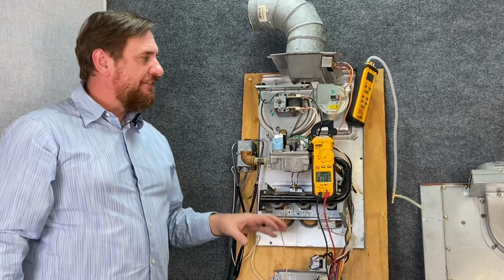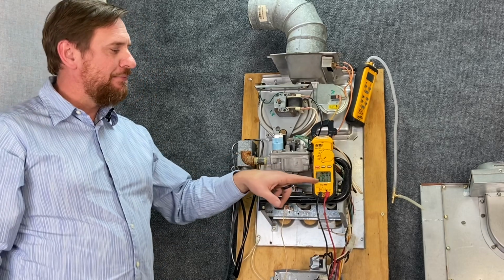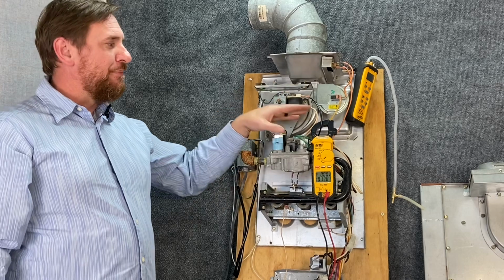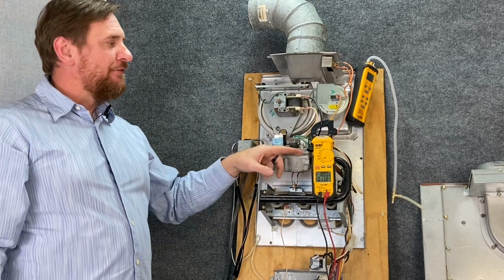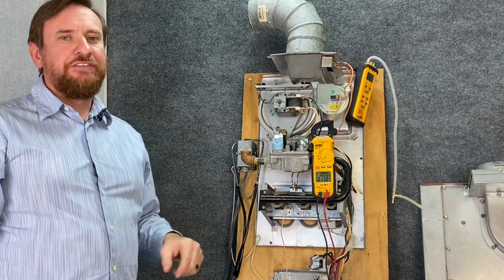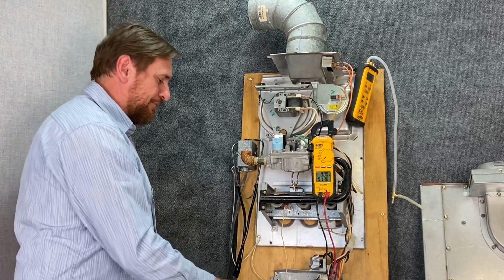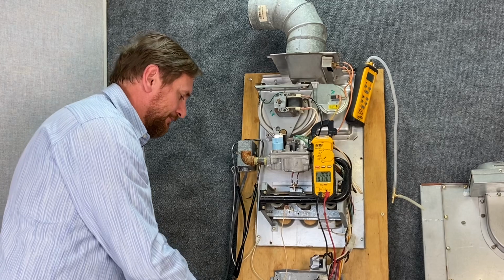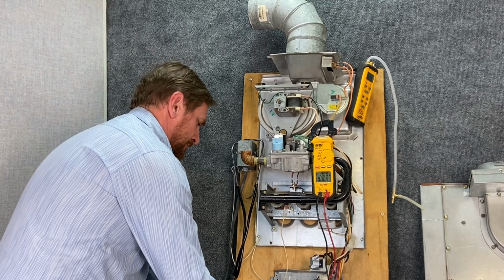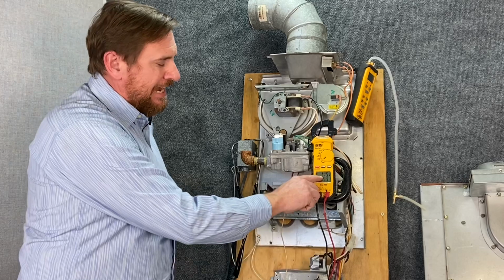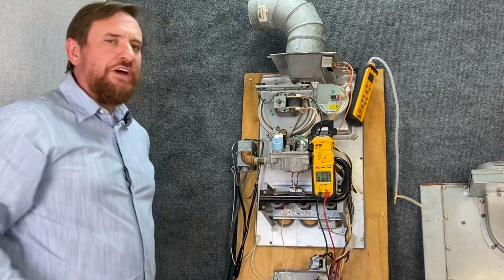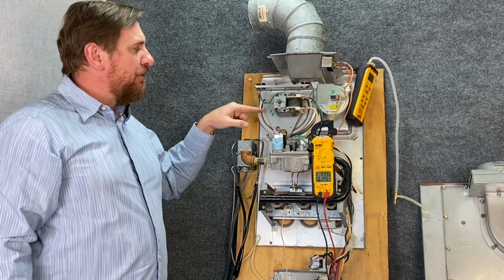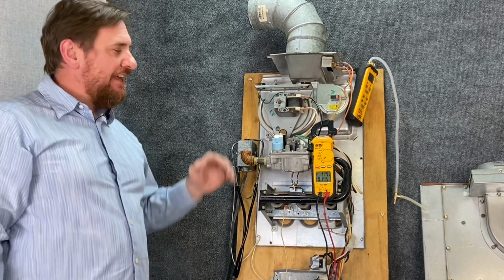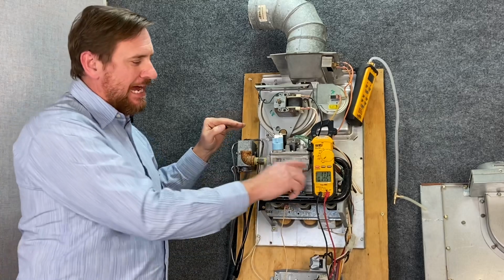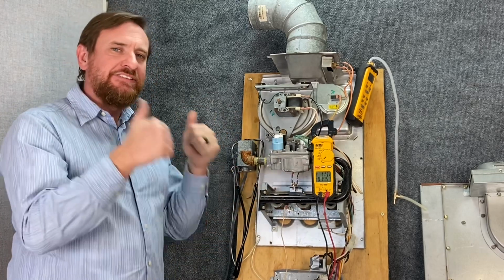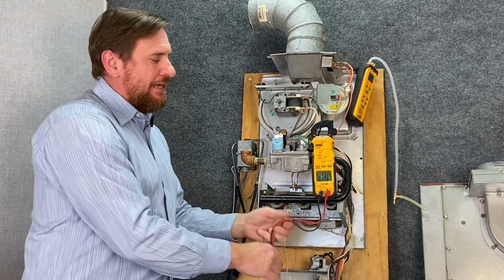What we're going to do next is we're going to fire the system up. We're going to check the amps with my top and we'll check voltage at the bottom. Remember, we need to have the proper amps without overamping, the proper voltage, and also we want to make sure we're pulling the proper vacuum to that pressure switch. So I'm going to have it call for heat. The amperage I'm pulling right now is 1.15 amps. I check on the motor and the motor's rated for 1.8. 1.8 is my max. I'm at 1.1, I'm well below my max. That's a good sign, that's what we're looking for.